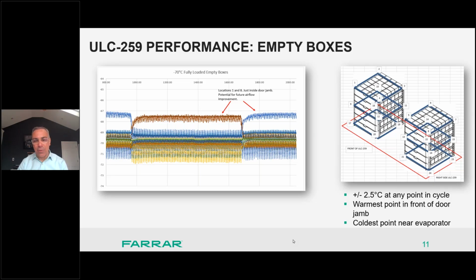And what you'll see here is that we're at plus or minus 2.5 degrees, with the warmest points right in front of the door, as you can see right by that top bar at the top. And so in fact, without including the door, we're back at that plus or minus 1.5 C from the empty chamber. So let's look at an even warmer set point next.